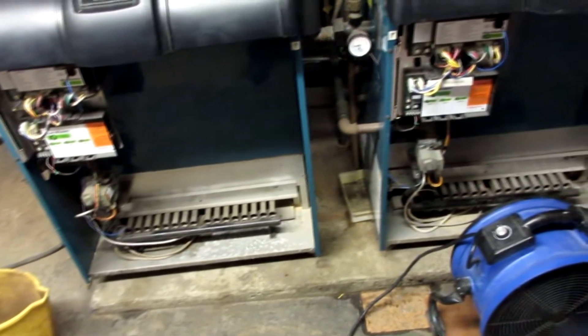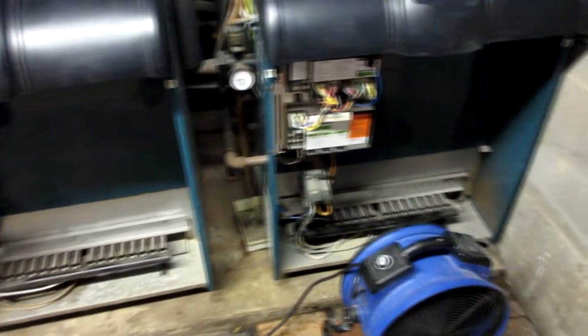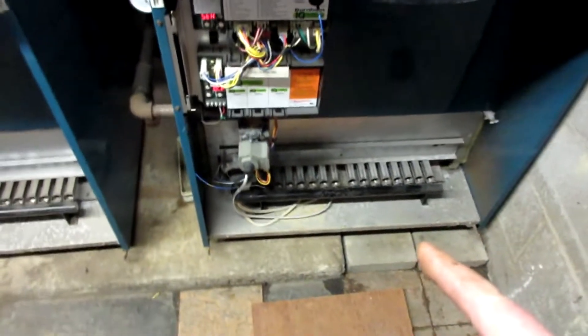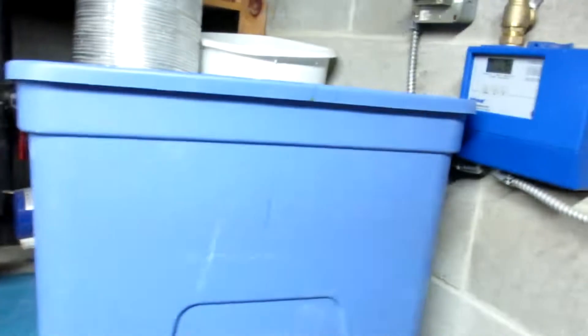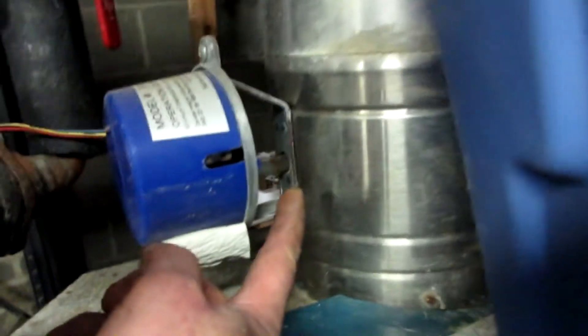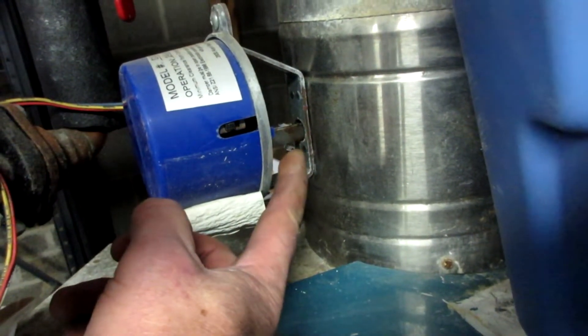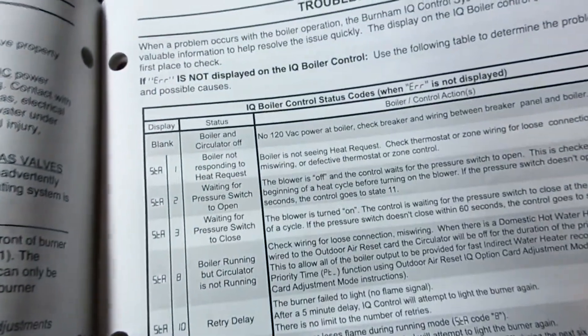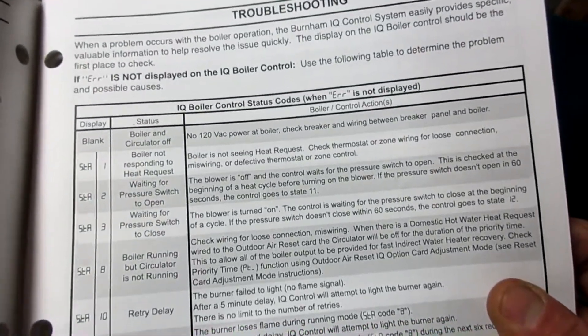The first thing is just trying to dry these out — both of them were wet internally. I dried this thing out, monkeyed with a bunch of wires, and went to start it. It tried to start — this thing right here is the damper — it opened up, I heard it turn open for the exhaust, then it shut off and it was throwing a different code: SEr 1 — boiler is not seeing heat request, check thermostat or zone wire for loose connections.